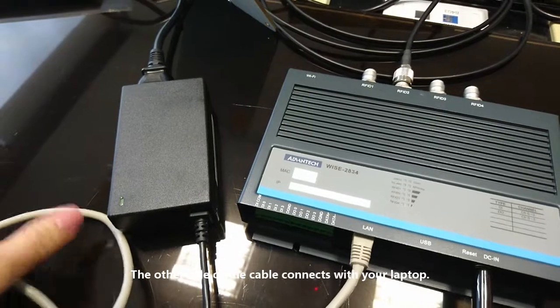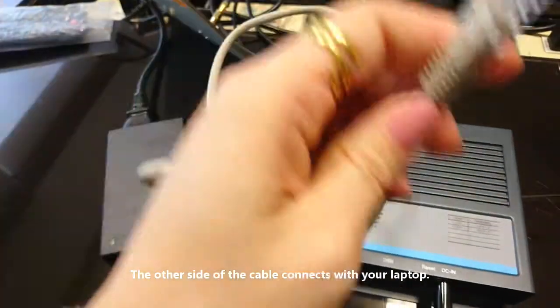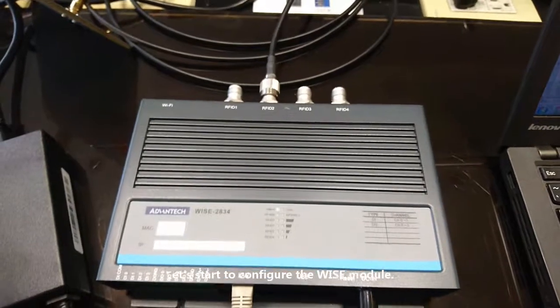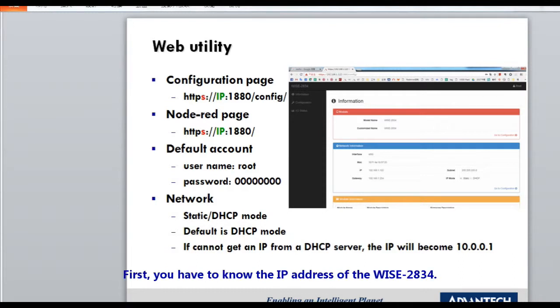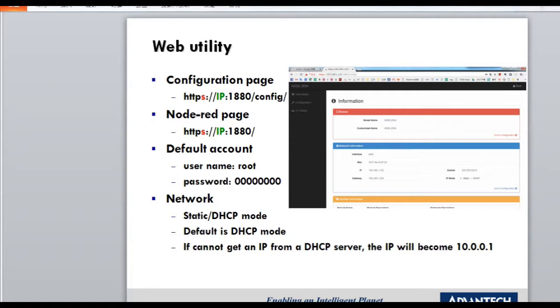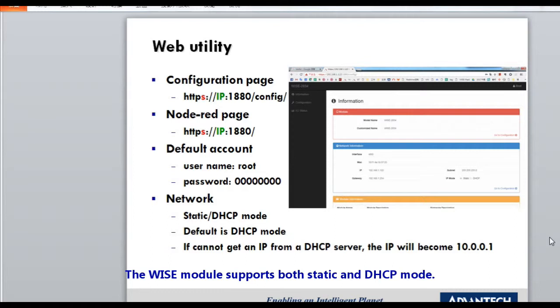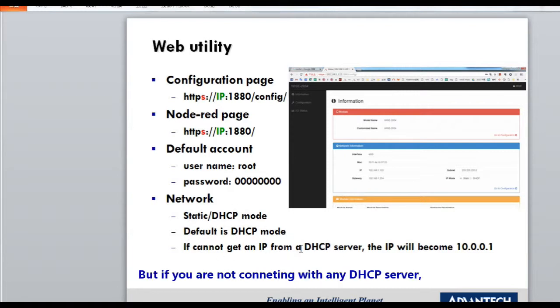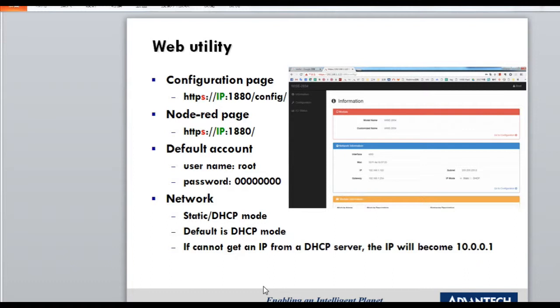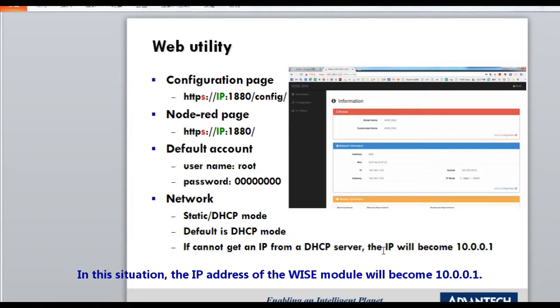The other side of the RJ45 cable connects to your laptop, and now we start to configure the WISE module. To log in to the web utility, you first need to know the IP address of your WISE 2834. The module supports both static and DHCP mode; the default is DHCP mode. But if you are not connected to any DHCP server, the WISE module cannot obtain an assigned IP address. In that situation, the IP address of the WISE module will become 10.0.0.1.